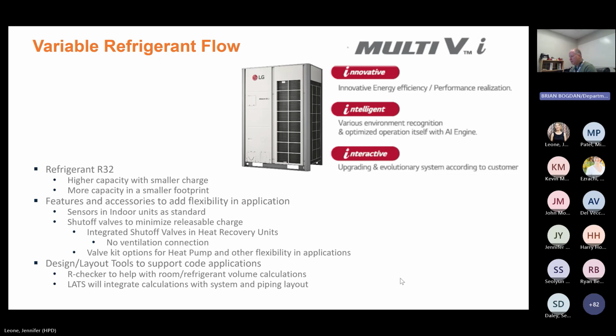What counts as a connected space and various other things factor in. So the refrigerant concentration limit you end up with is significantly less than LFL. In certain situations the baseline is more like 25% of LFL, and you may be closer to 50% of LFL with certain requirements resolved. I'd also like to point out that UL has very specific requirements for designing products in ways that can be applied safely within the standard.